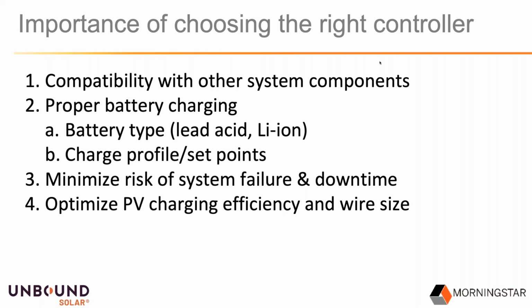Lead acid is the most common. Lithium ion has also grown in popularity. Some controllers are only built or designed for lead acid. So unless those charge set points or profiles are adjustable, you might not be able to do lithium ion on every controller. You might not be able to charge those batteries. And of course, even with lead acid, there's different charge profiles or set points that we want to make sure we can accommodate. The third on the list is just to minimize risk of system failure and downtime.